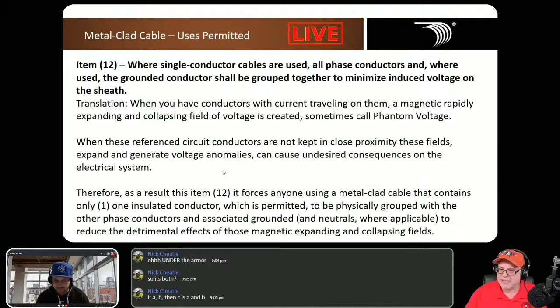So many people ask me, do they make an MC cable with only one single conductor in it? And yes, they do. And they ask, where would you ever use something like that? Well, this is an example when you'd use it: for, say, a 2-hour fire resistive cable. Now this is an example of an actual armor that is continuous, smooth. You see that there's no welds there. That's a continuous extrusion, and it has a single conductor in it. Now this gets tested under UL 2196 to meet what's called a 2-hour fire resistant cable. And if they had the need for 3 hots and a neutral, then they would run 3 of these independently with a separate neutral, and they have to keep them in close proximity. That's what item 12 was all about.